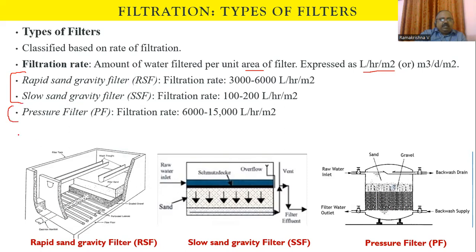The filtration rate for a rapid sand filter is around 3,000 to 6,000 liters per hour per square meter. For a slow sand gravity filter, you can apply only 100 to 200 liters per hour per square meter. For a pressure filter, the rate goes up to 6,000 to 15,000 liters per hour per square meter.